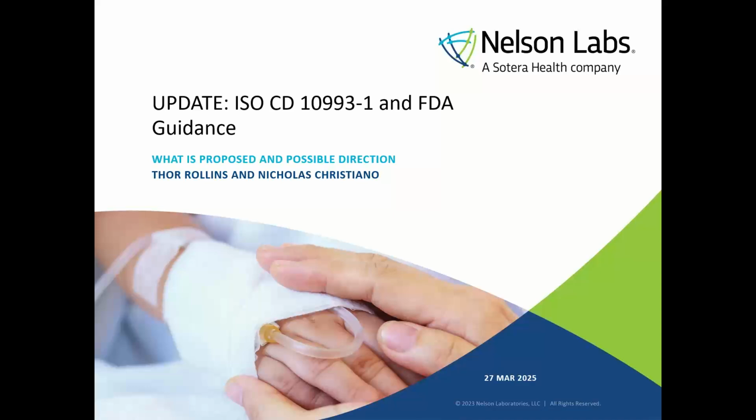Yeah, and all I would add to that, as you mentioned there, Thor, is that there is a little bit of guidance within this update to the standard which points to the use of post-market surveillance. As we are creating line extensions or product changes over time, it may be hindered a bit with new product development outside of the realm of line extensions. But for devices that have post-market surveillance data that can be leveraged, like complaint rates, things like that, I think that is another way to assess biocompatibility of those long-term implants as well.